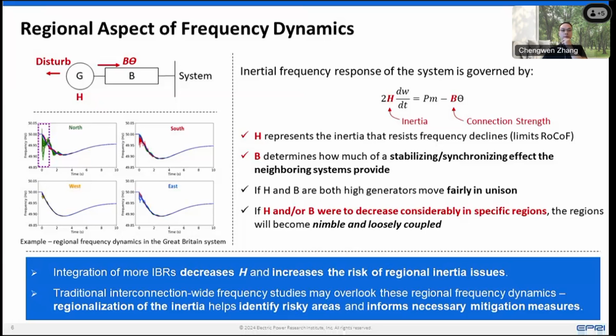This is exactly what we want to focus on with this inertial regionalization topic, because inertia is not distributed evenly across the system. You can have weakly connected regions with low regional inertia levels, and nowadays we have more and more IBR integration. If they're concentrated in the same location, that can pose more risk on that region to have lower inertial levels, and these dynamics may not be fully captured in traditional interconnection-wide frequency studies.